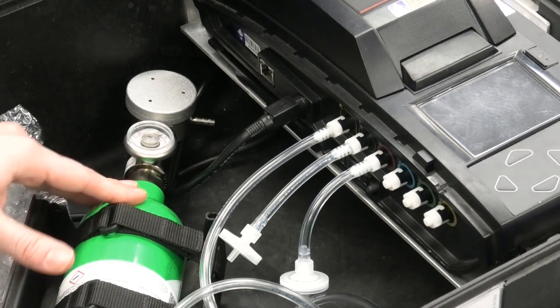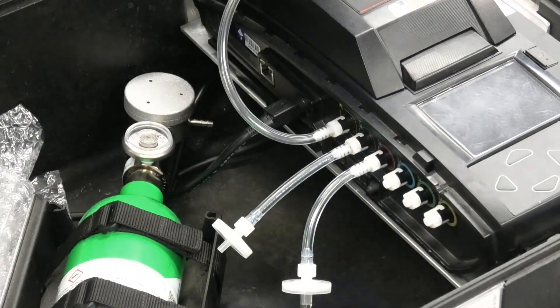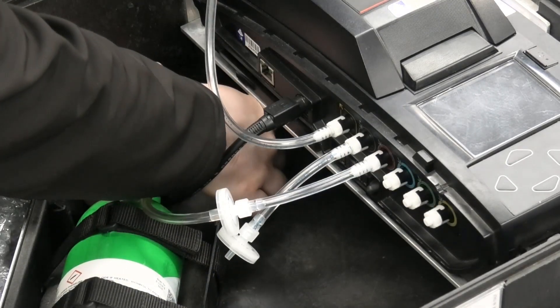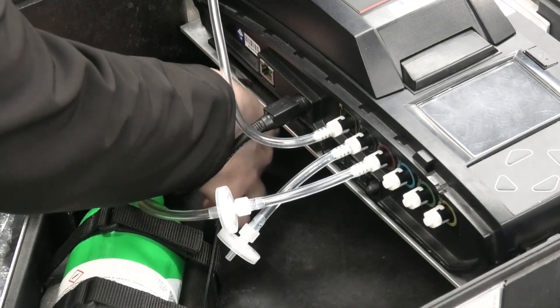Put the belts on so it's in a secure position, and then what comes next is that we let the exhaust hose out and then connect the gas inlet to the regulator, to be able to apply the gas when we're doing the bump and calibration.